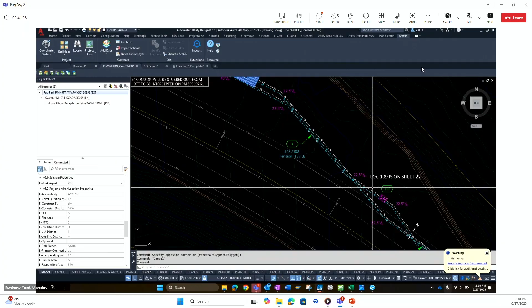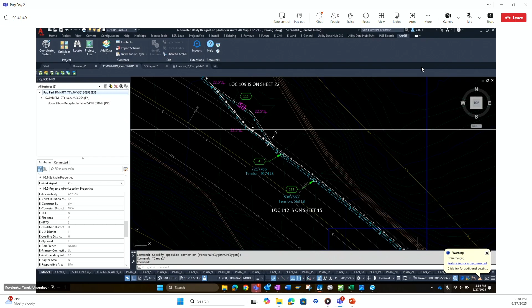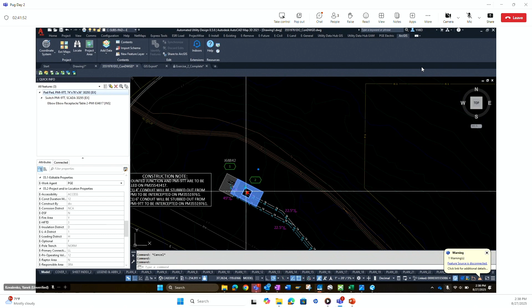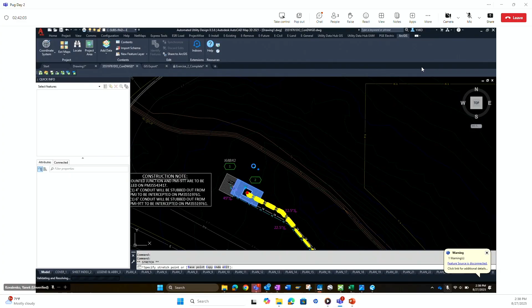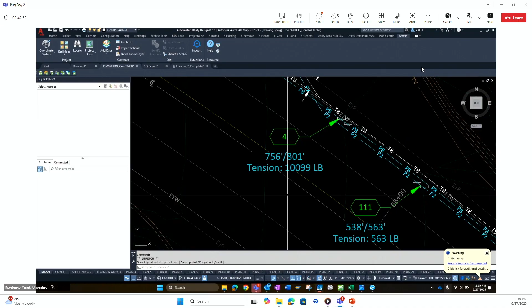So for example, right here at location 4, has 721 foot of conduit, 766 feet of cable, and that's the tension, 9,574 pounds. If I was to move something just for demonstration purposes, AUD will recalc, it will run through analysis, figure out whether I'm exceeding bends. We're not even talking about validations, but it would run through validations of, hey, are you pulling more than minimum required length? It would run through all the validations, run through the calculations, and update our conduit length, cable lengths, our tensions, which would also be in the preferred direction, and reverse tension as well. So we made that change without doing anything manually. We got updated information at location 4.